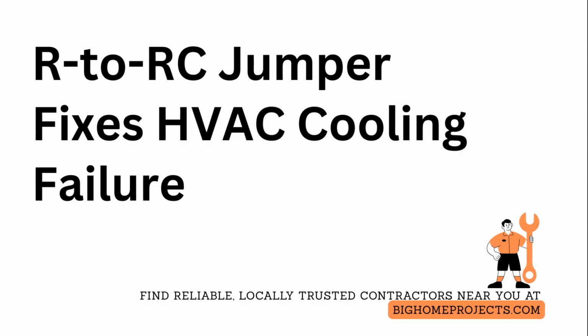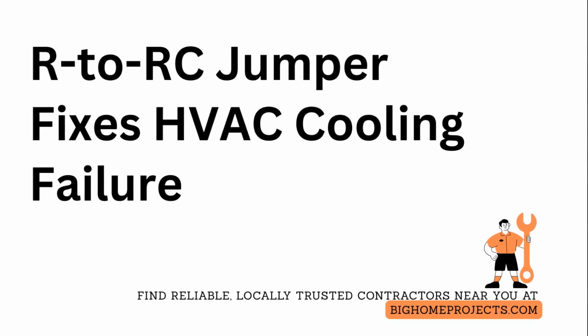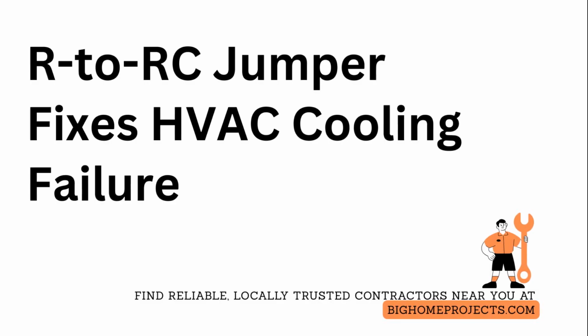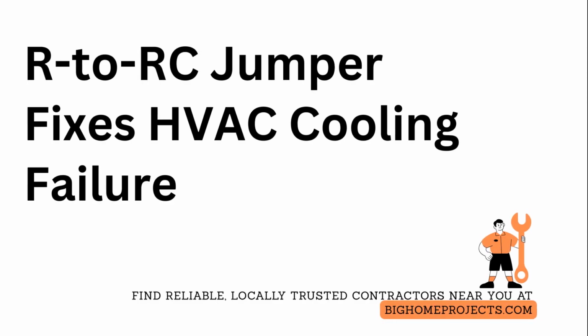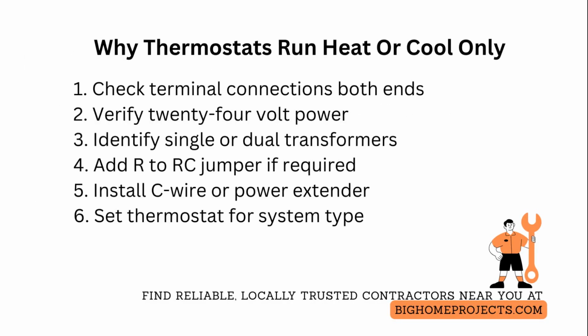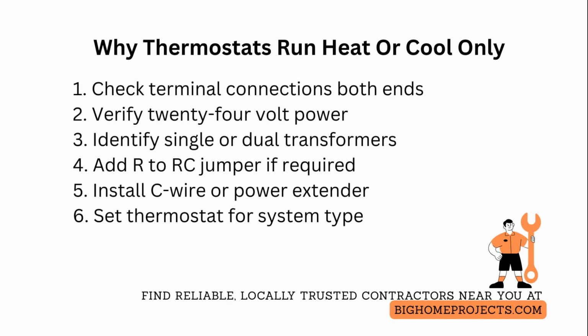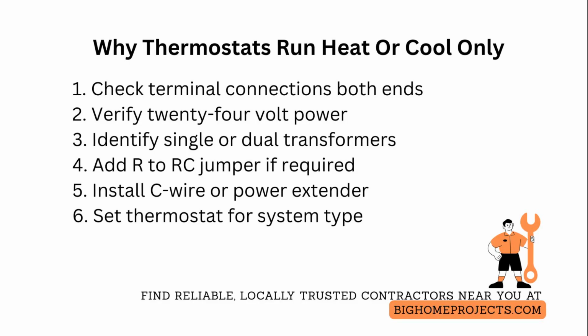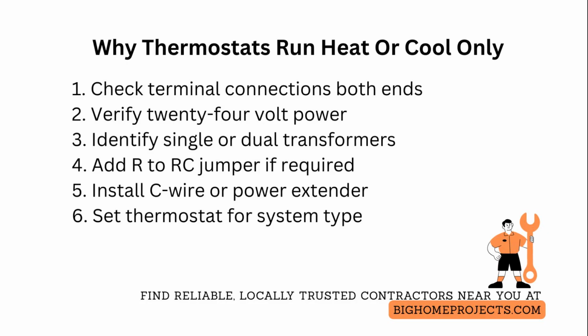Thermostats that only run heat or cool after installation usually point to wiring or compatibility issues, not a faulty thermostat. When a thermostat controls only one mode, first check the terminal connections at both the thermostat and the air handler or furnace. Confirm that power is present on the red terminal and that the cooling coil conductor, often labeled Y, and the fan conductor, often labeled G, are securely attached and show continuity back to the equipment.